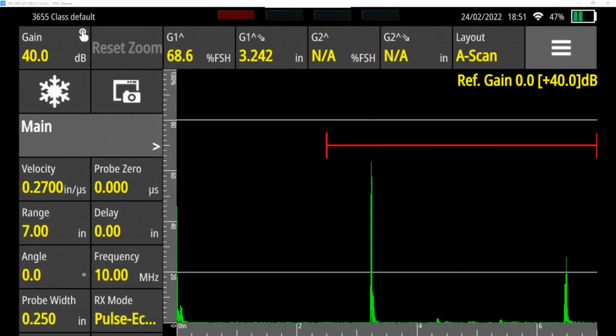Now we need to start calibrating our velocity. So the difference between the back wall echo and a secondary back wall echo should be exactly 3 inches. Right now, our primary back wall echo is 3.242 inches.